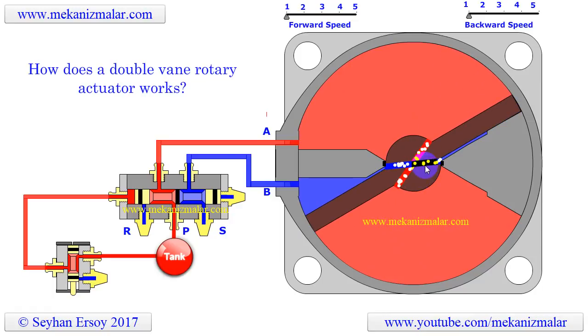Also, with the equal pressure force acting on two opposing sides of the vane, the torque exerted on the rotating shaft is doubled with respect to a similar sized single-vane rotary actuator.